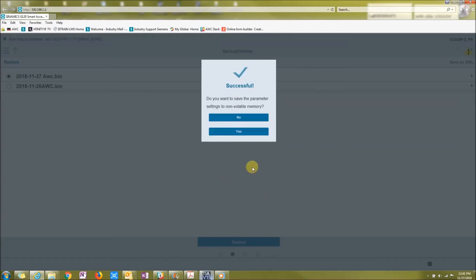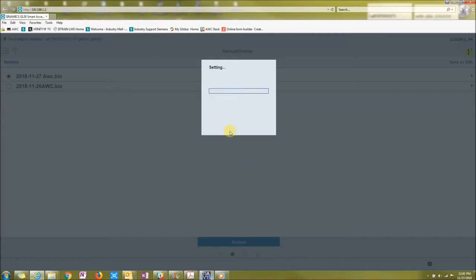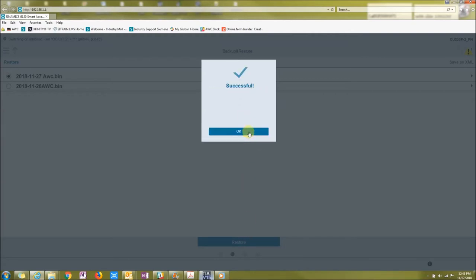This will put the parameters from the bin file into the drive now. Now it will say, do you want to save the parameter settings to the non-volatile memory? So RAM to ROM, I'm going to just say yes. So now I'll do a RAM to ROM function. OK.